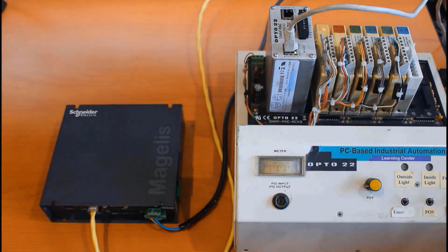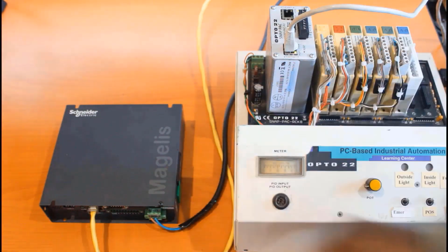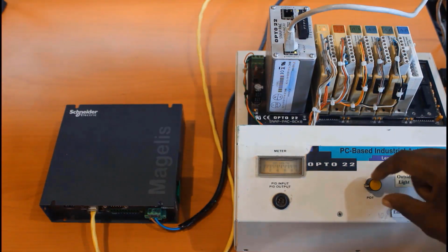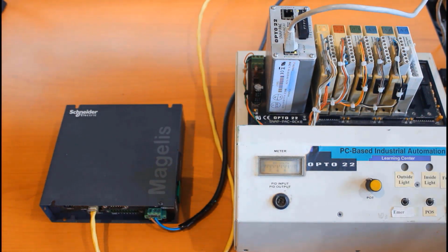In this video, I'm going to show you how to monitor plant flow data in real time using MQTT, InfluxDB time series database, Grafana Visualisation platform, Schneider IIoT Gateway, and HiveMQ Cloud as the centralized MQTT broker. And for demonstration, I'm going to use this Schneider IIoT Gateway to collect tank level telemetry data simulated by this potentiometer on this legacy controller via Modbus TCP.